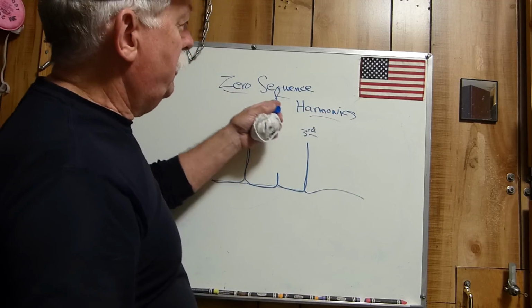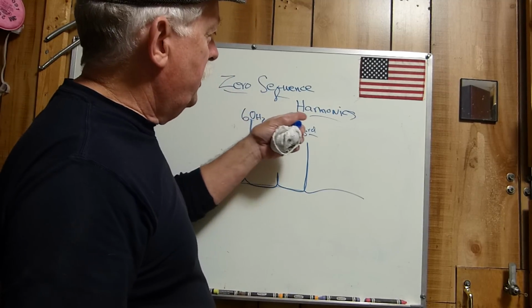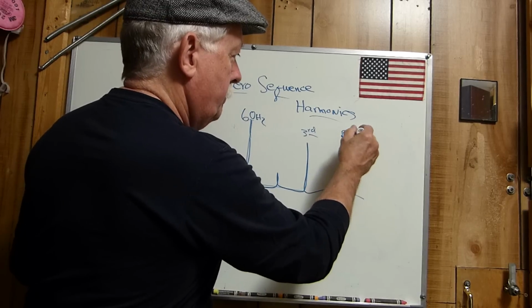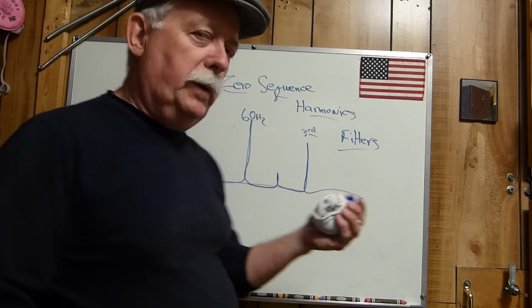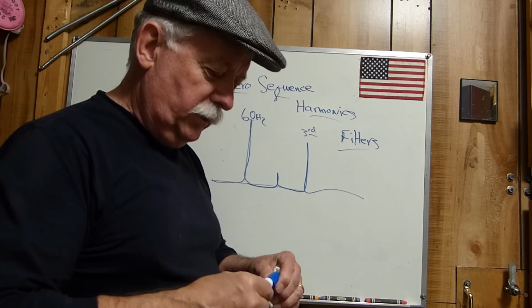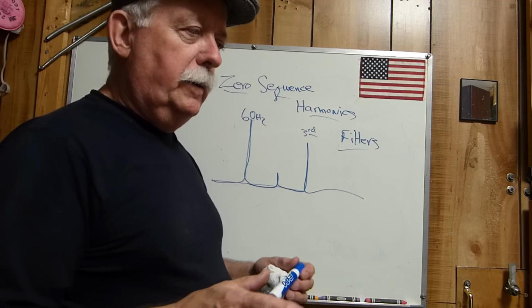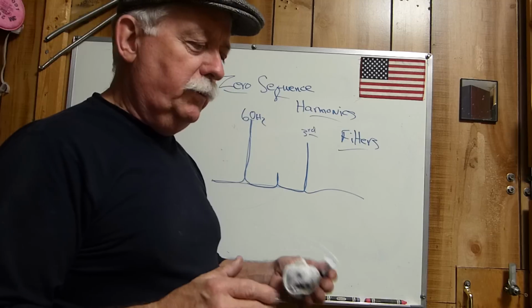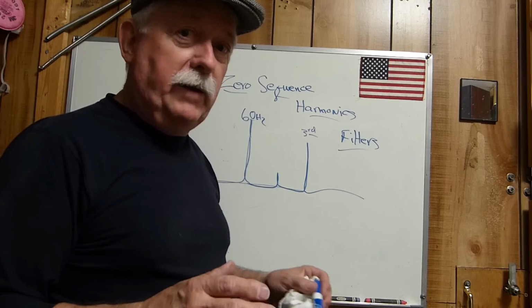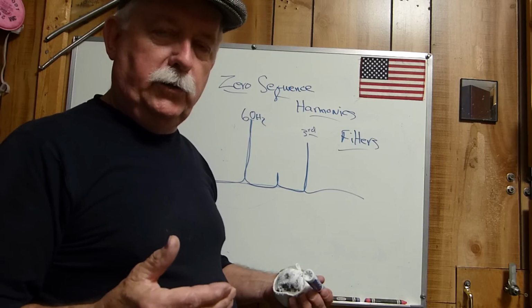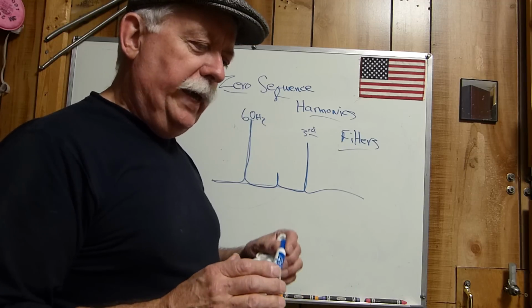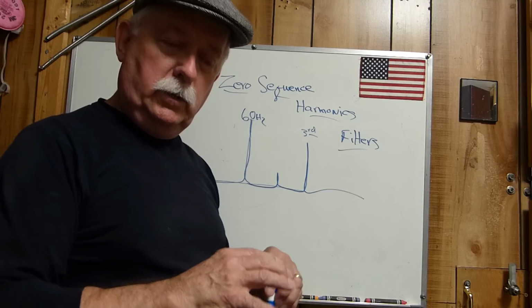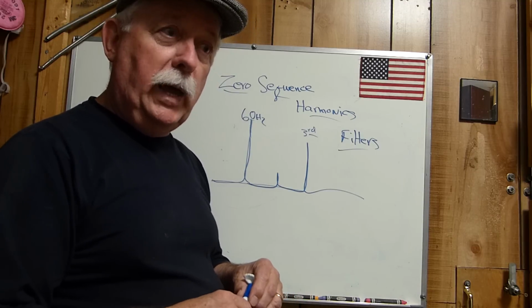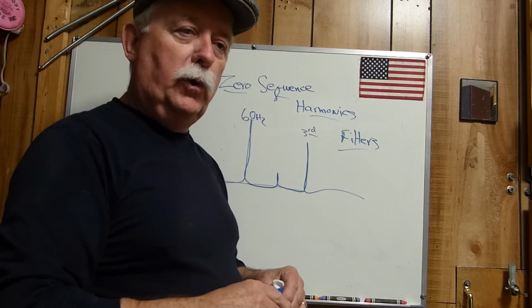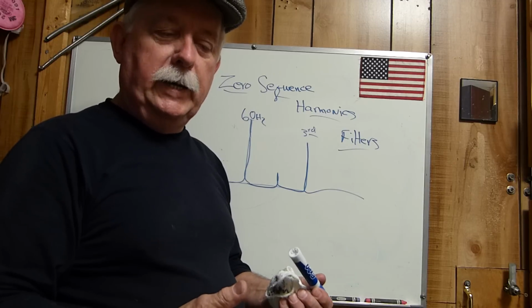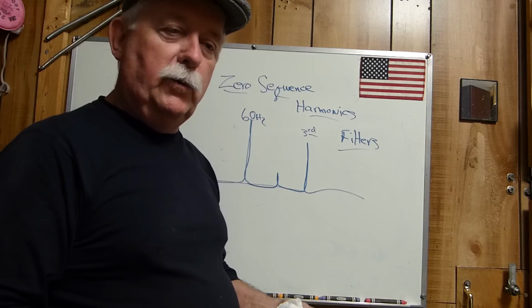Zero sequence harmonics are hopefully solved by zero sequence harmonic filters. Most of these filters are great big things that feed factories and large installations, but I saw one on eBay the other day. They're not cheap - it was about $750, probably in the 3, 4, possibly 5 kVA range, something people like us could afford. They also made a point that it worked even at low secondary loads, implying that the big zero sequence harmonic filters only work well when loaded to their rated current. They claim theirs works even at low current, so that might be what you need.